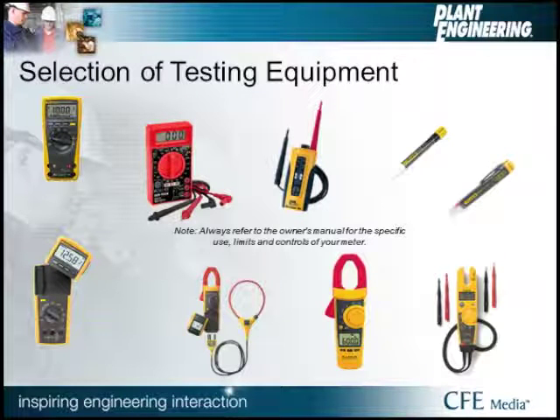In addition to our multimeters, we have solenoid testers, we have clamp-on meters, and finally we have the voltage detectors. Now I hear a lot of people talk about these voltage detectors in a bad way. They have their purpose, but we have to understand the limits of a voltage detector. It's used to determine that power is on. It cannot be used to determine that the power is off.